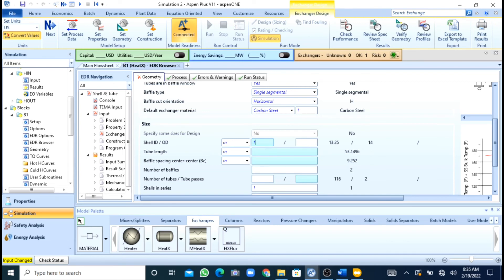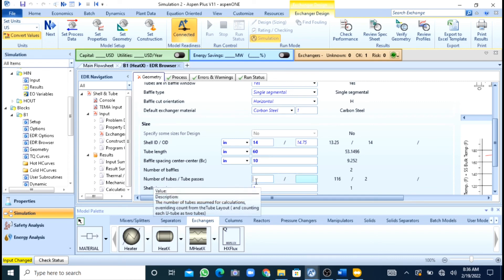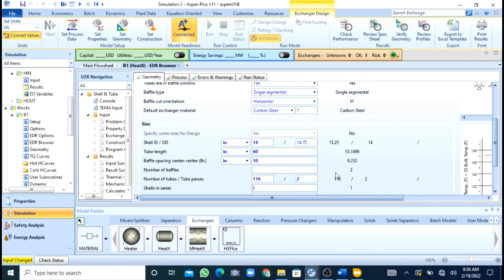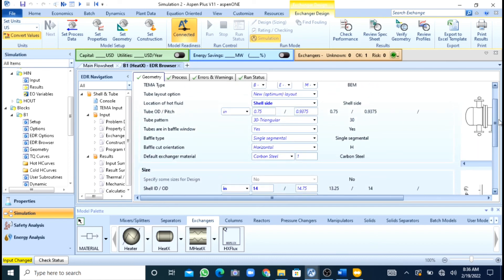I want my shell outer diameter to be 14 inches. Tube length — I want my tubes to be 60 inches long. Baffle spacing I will take as 10. Number of tubes I will set as 116. Number of passes I will set as 2. After this I will press the run button.